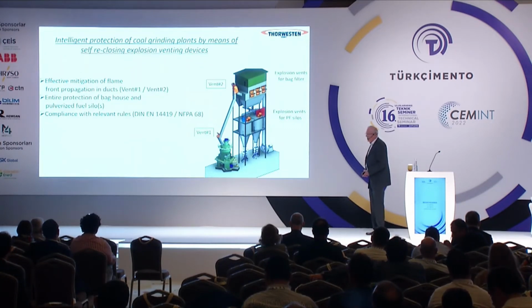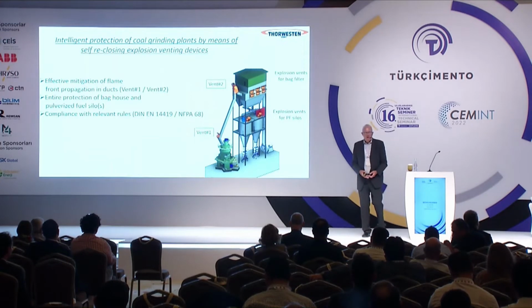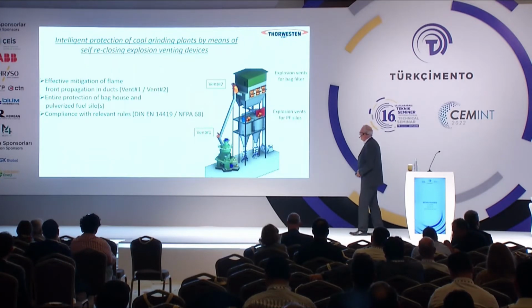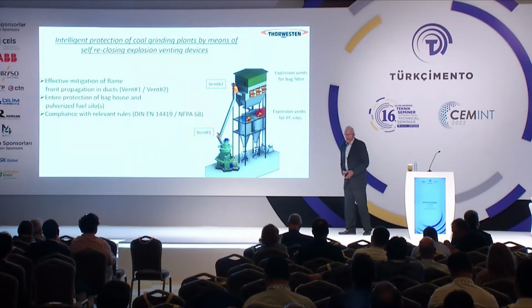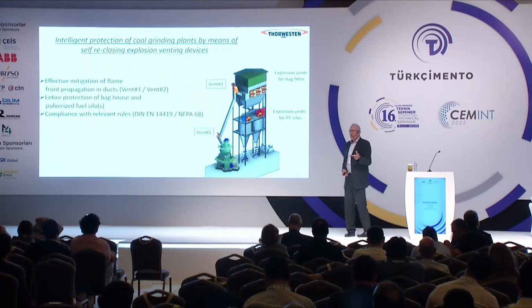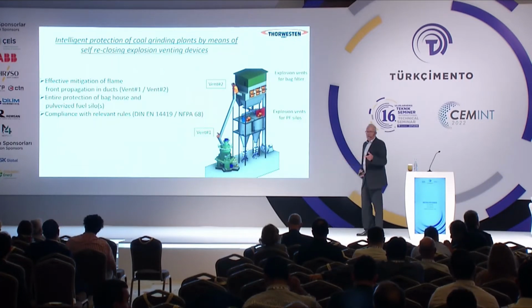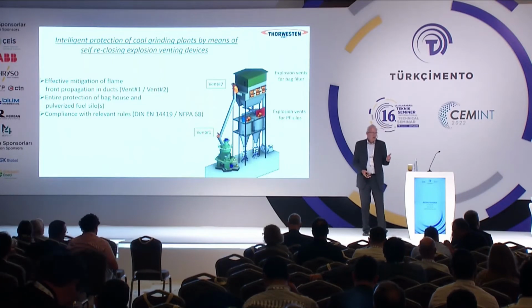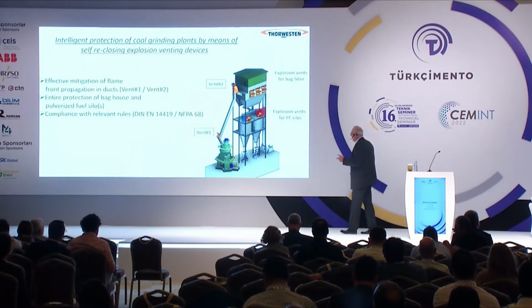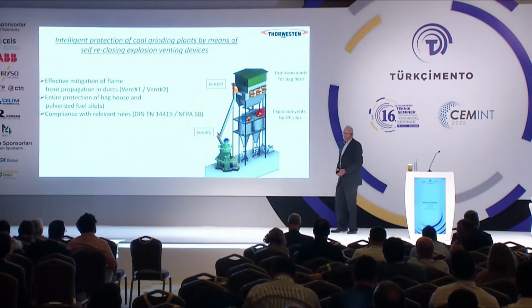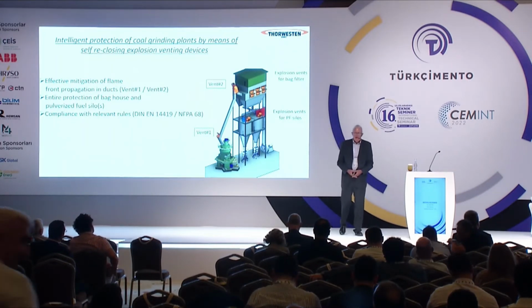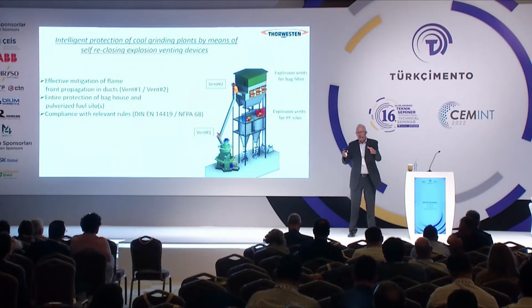When we are talking about vertical roller mills, as shown here, the concept consists of two independent working venting devices: one positioned very close to the mill outlet, and one designed and positioned in front of the baghouse, designed as an explosion diverter. The principle is as follows. In case of an explosion in the mill body, we analyzed that the pressure created in the mill body may reach a value of up to 2 bar g.